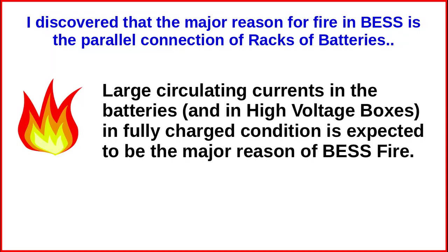I discovered that the major reason for fire in the BESS is the parallel connection of racks of batteries. Large circulating currents in the batteries and in the high voltage boxes in fully charged condition are expected to be the major reason of BESS fire. The circulating currents are not transient. I found the circulating currents to be continuous in nature, which can damage the batteries apart from causing fire.